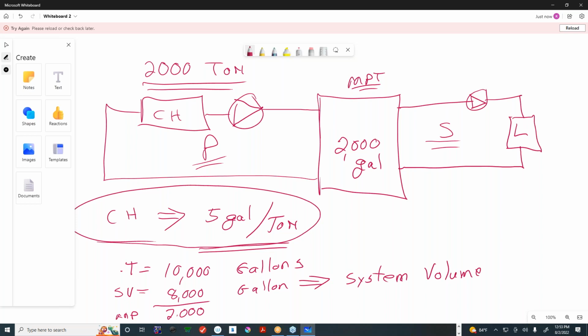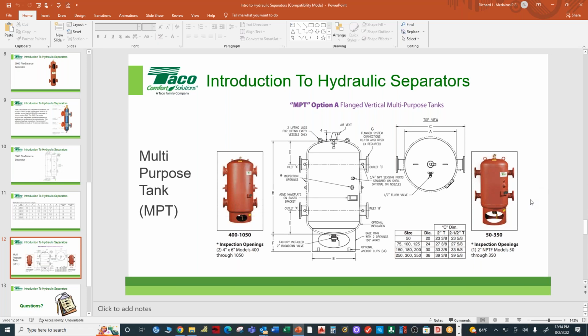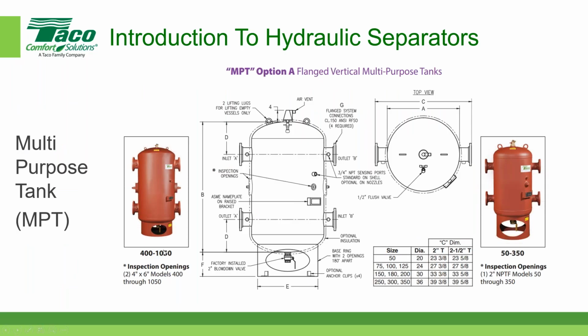So this multi-purpose tank can work as a hydraulic separator, as a buffer tank, and as an air and dirt separator. It has all three functions. From a simplicity standpoint, you specify something like that and it takes care of all of those components. Your bridge is installed correctly, and you don't need air and dirt elimination on either side, primary, secondary, or both. That's right, there are a lot of inherent benefits to those three items. And as I say all the time, you never do this kind of design work in a vacuum. You also always make sure you have the appropriate configuration and sizing based on manufacturer's recommendations.